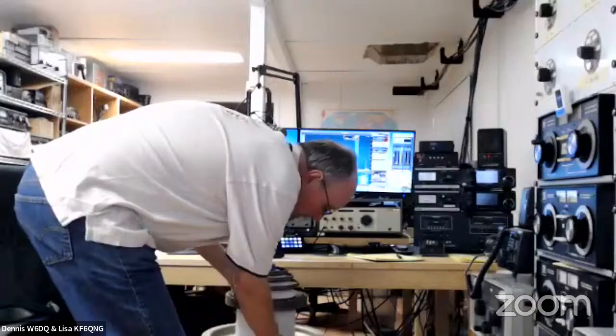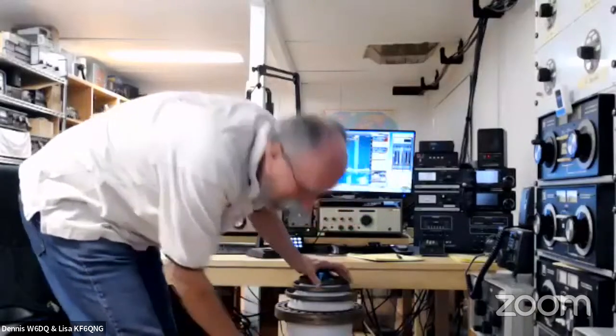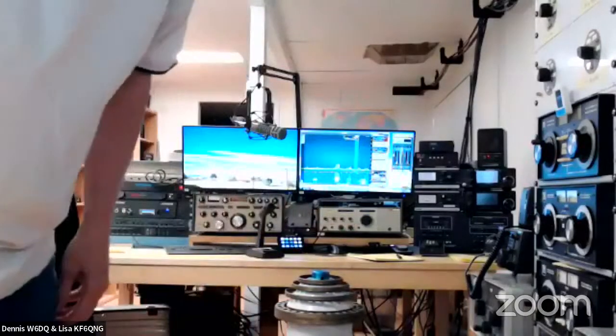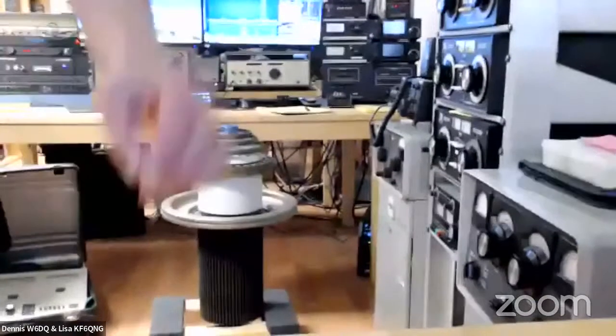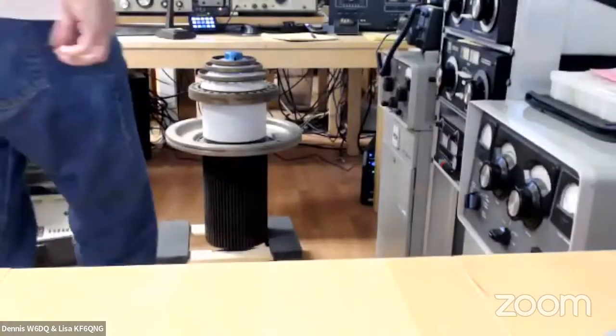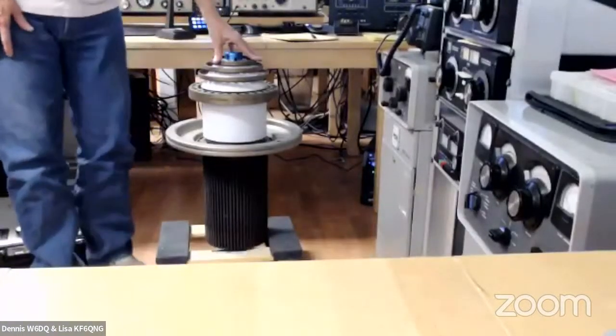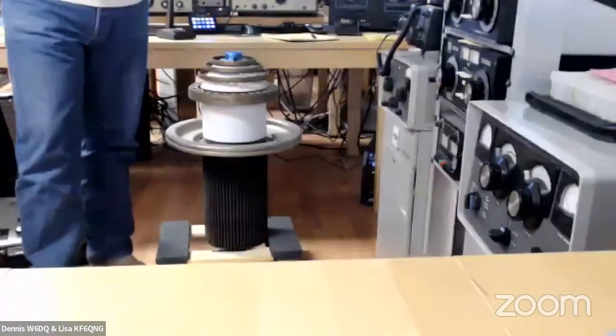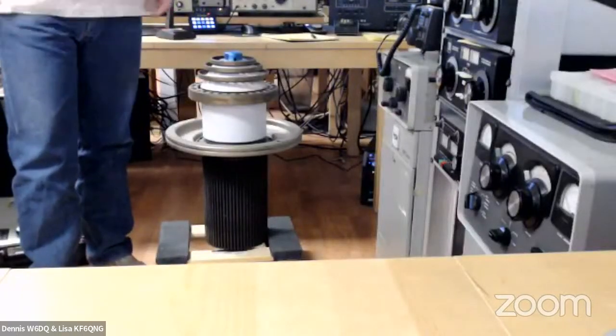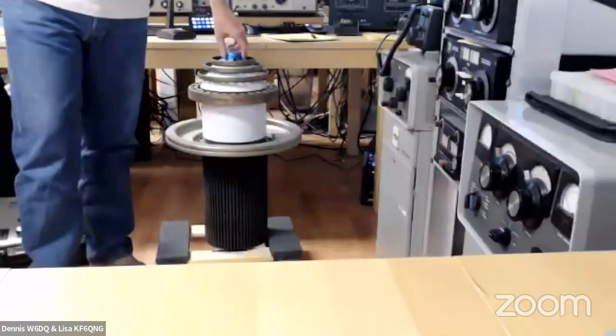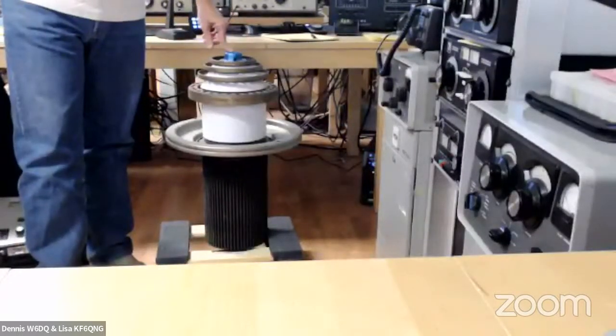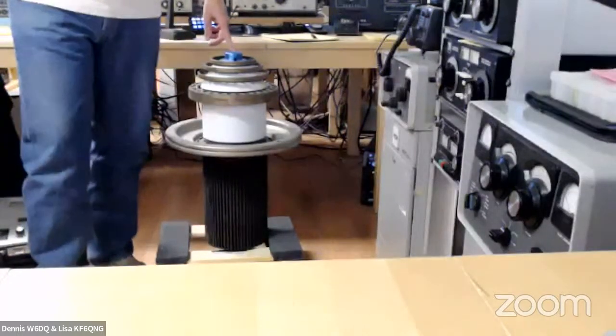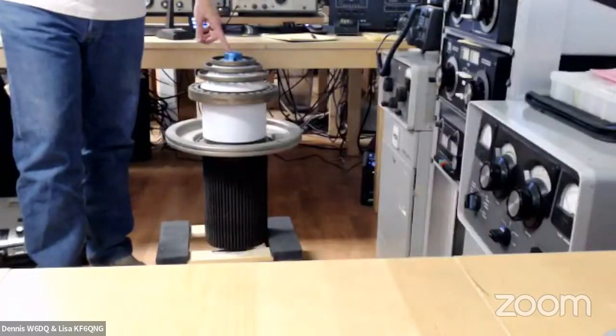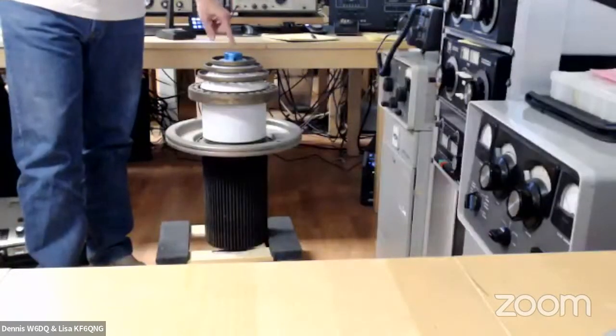What I want to show you, if you're curious about transmitting tubes, there's a little transmitting tube right there. Now this isn't out of the Collins, but it's similar in design to the tubes that came out of the Collins transmitter. This came out of - there were 4 other transmitters on site made by a company called Brown Boveri out of Switzerland. They're also 250 kilowatt transmitters, but instead of being a high level plate modulated transmitter, they're pulse width modulated, so it uses a single output tube.